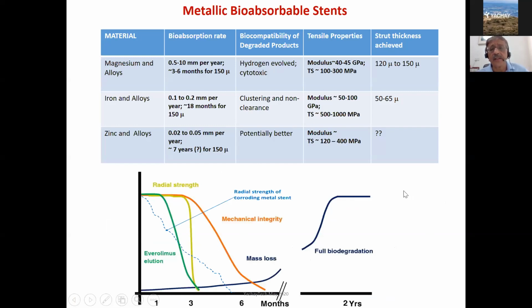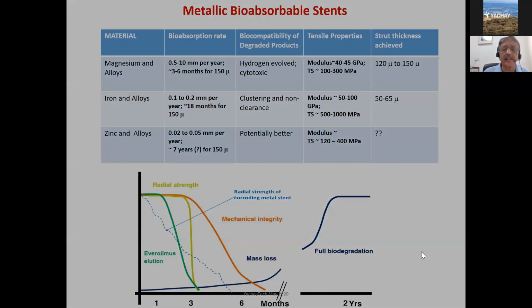So I'll just summarize the work here by showing the problems with the absorbable stents. The radial strength has to be maintained for at least 3 to 6 months, and then they can slowly start to degrade, while the tissue coverage starts to happen at about the same time and must be fully developed by 12 to 18 months. In the meantime, the radial strength is decreasing. For fully degradable metal stents, it's decreasing faster than it is for polymers, which have this bulk degradation mechanism. So it is more difficult to control the mechanical properties for fully degradable metallic stents. But people are working on this, so there is hope that low strut thickness stents can be developed and tested in the clinic very shortly.